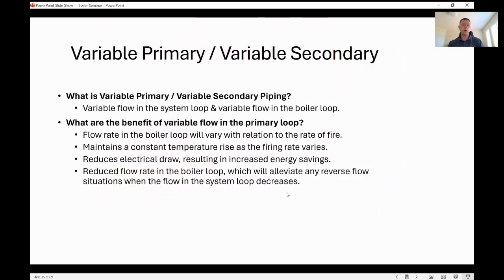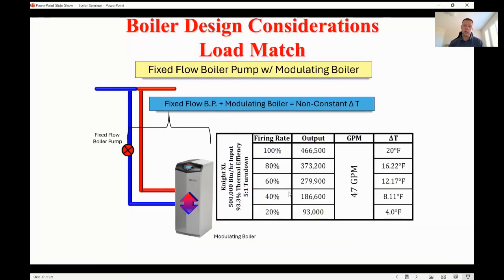And this is a kind of a cool way: variable primary, variable secondary piping. With this, of course, you're going to have your VFDs on your system loop, but you can also have VFD pumps on the boiler loop. And what's happening here is the boiler will drive this. As that boiler ramps down, it's going to ramp its boiler primary pump down, keeping a constant delta T, and you're going to achieve some electrical savings by doing this.